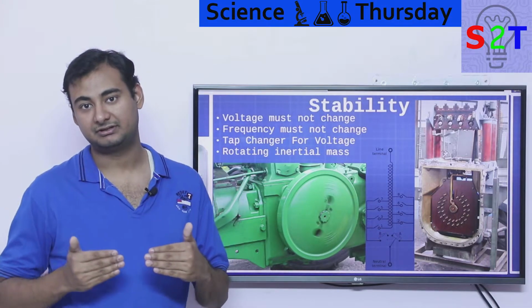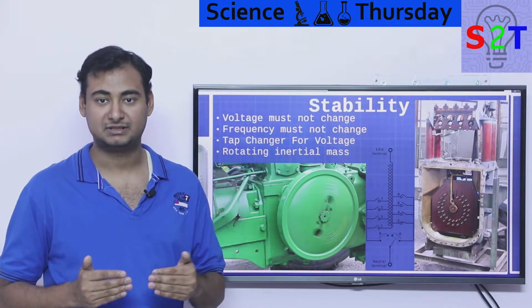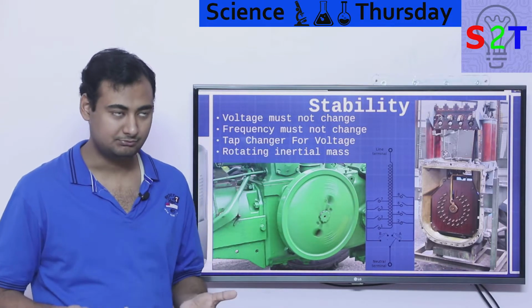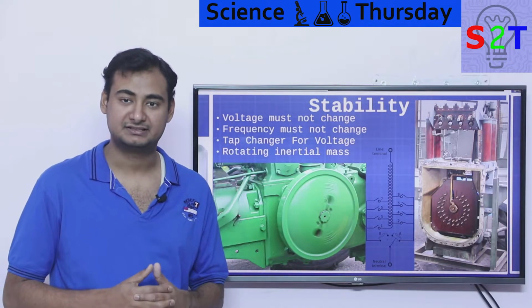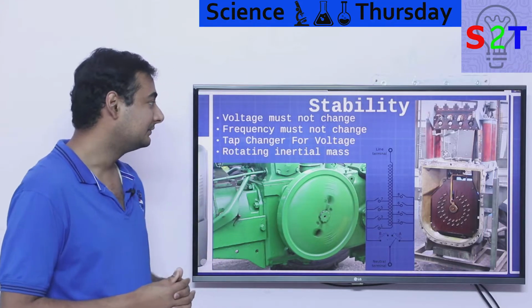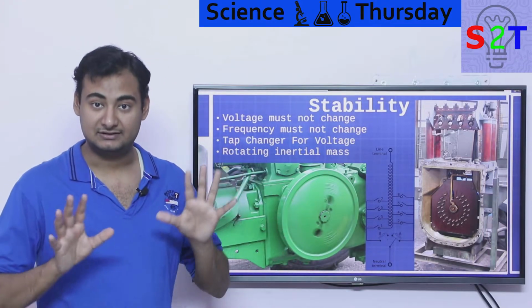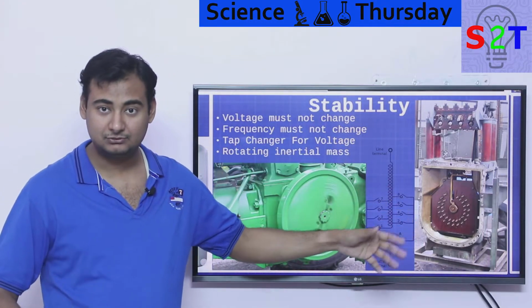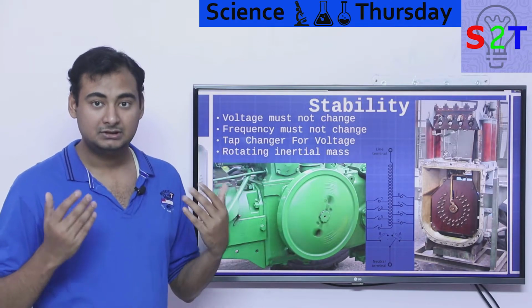Of course, modern inverters have fail-safes. If they detect the frequency going below a few percent plus or minus, they will cut the signal, because people learned the hard way that things catch on fire when frequency changes. So this is how we are stabilizing our grid as of now. We have tap changers to handle voltage, and we have giant spinning mass to give us time.